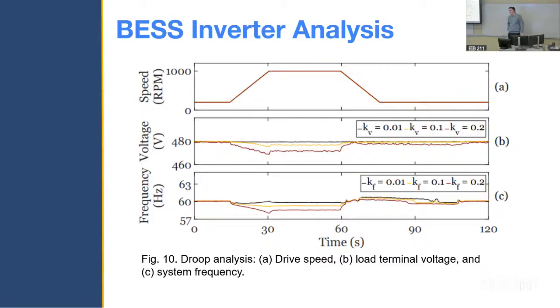Obviously, inverters aren't inertial-based systems like diesel generator sets. So what we do is play with the droop, which effectively mimics how an inertial-based generator would slow or speed up depending on the load. We went through a range of droop coefficients to make sure of that.